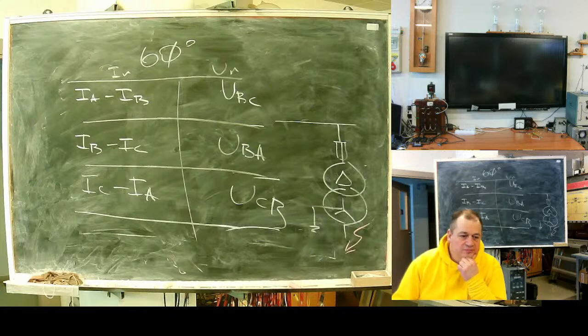Line-to-line faults. Line-to-line fault. Transformer with star-delta connection. Fault on the star side. What will happen?